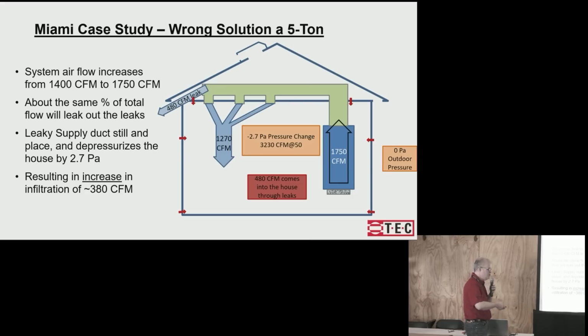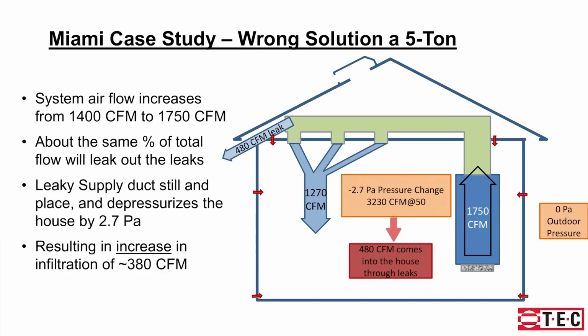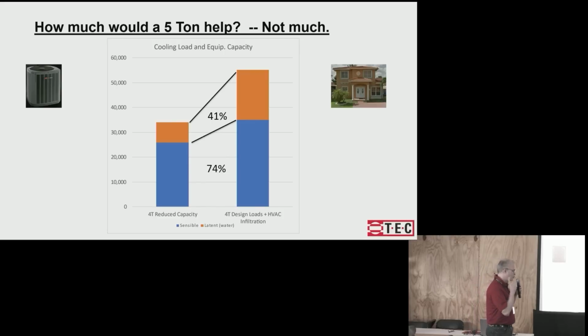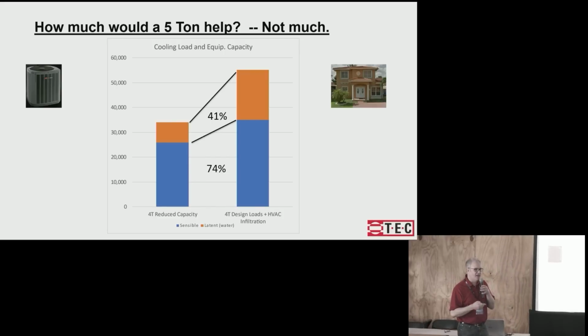Now, what does this do to the loads? So we explain what's happening. We're sucking more air in from outside. Now we've got 480, almost 500 CFM coming in from outside. Okay, so let's look at the loads here. Remember this chart? This is the 4-ton. This is what we really have with that 4-ton that's in there. We swap it out for a 5-ton. What do you guys think is going to happen? Going to cover it? There's going to be humidity issues. Yeah.